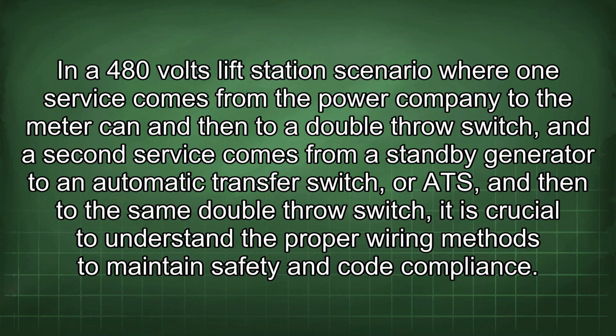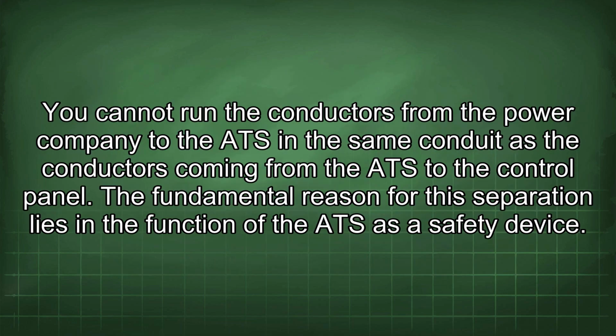In a 480 volts lift station scenario where one service comes from the power company to the meter can and then to a double throw switch, and a second service comes from a standby generator to an automatic transfer switch, or ATS, and then to the same double throw switch, it is crucial to understand the proper wiring methods to maintain safety and code compliance. You cannot run the conductors from the power company to the ATS in the same conduit as the conductors coming from the ATS to the control panel.